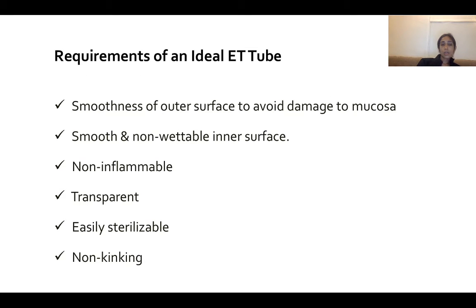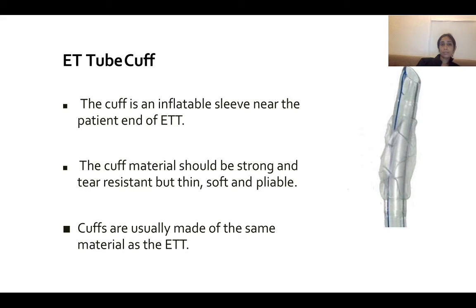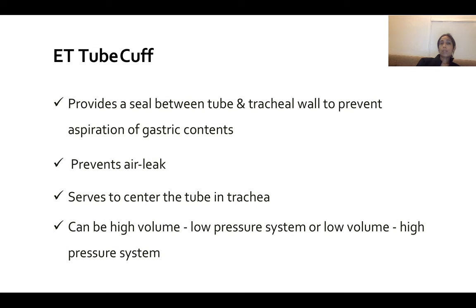So the requirements are that they should be non-kinkable and easily sterilized. They should be able to be sterilized easily. They should be transparent, non-inflammable, with smooth and non-wettable inner surfaces, and a smooth outer surface to avoid any damage to the mucosa. The cuff is an inflatable sleeve near the patient end of the endotracheal tube. It should be strong and tear resistant but thin, soft, pliable. Cuffs are usually made of the same material as the endotracheal tube. The cuff provides a seal between the tube and the tracheal wall to prevent aspiration of gastric contents. It prevents air leak. It serves to center the tube.